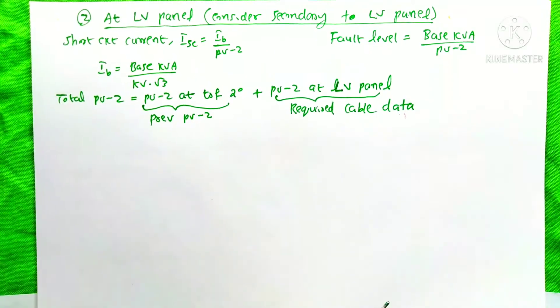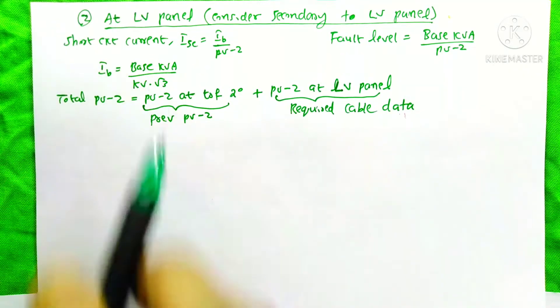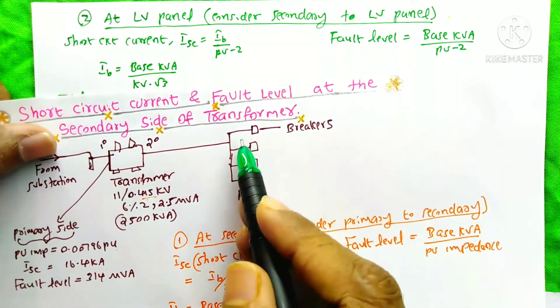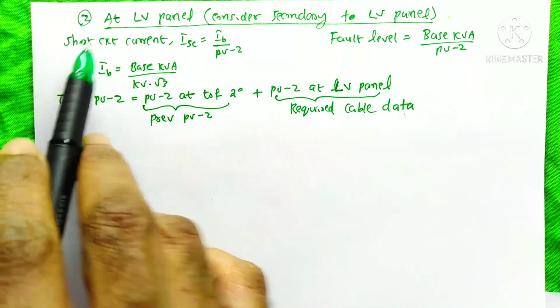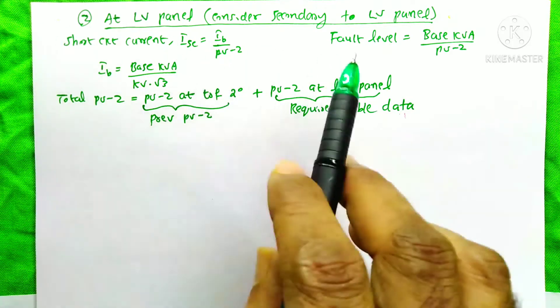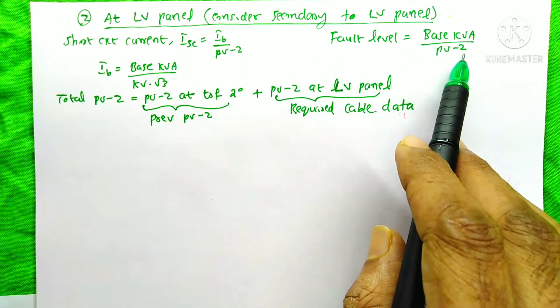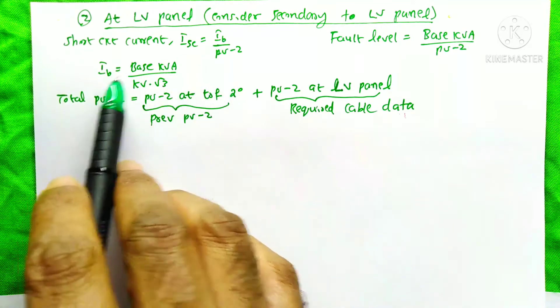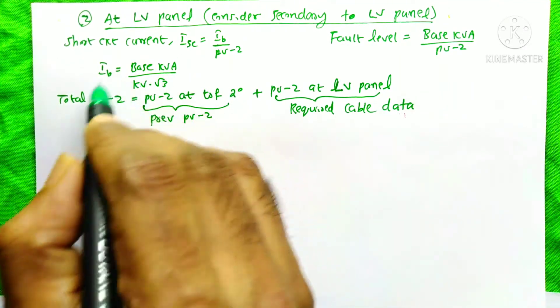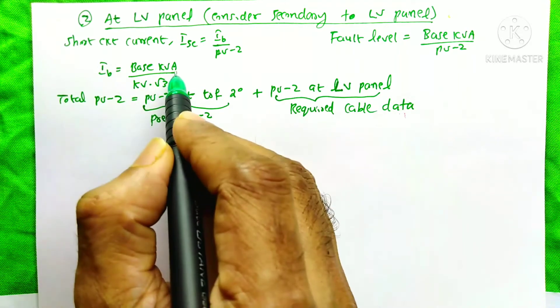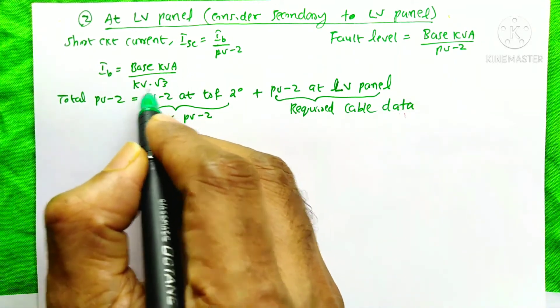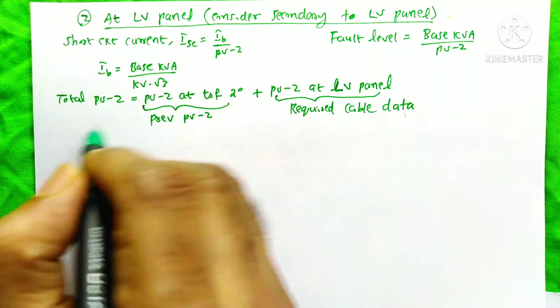Now we are going to calculate the short circuit current and fault level at the LV panel. The equations are: ISC equals IB divided by per unit impedance, fault level equals base kVA divided by per unit impedance, and IB equals base kVA divided by kV into root 3. The IB has no change because the base kVA is the same — 2.5 MVA — and kV is still 0.415. So we need to find the per unit impedance.